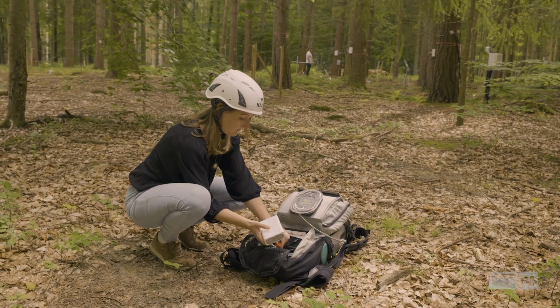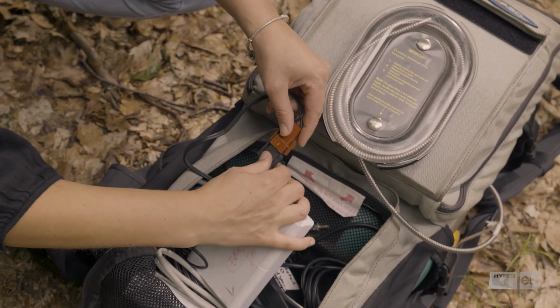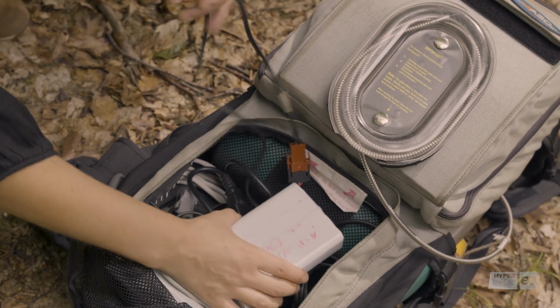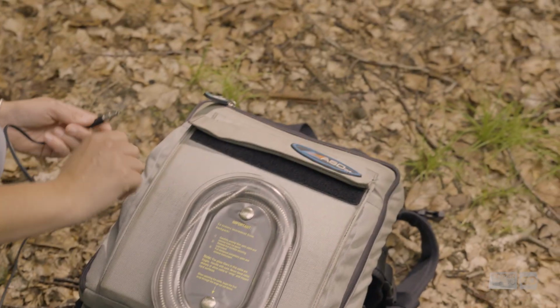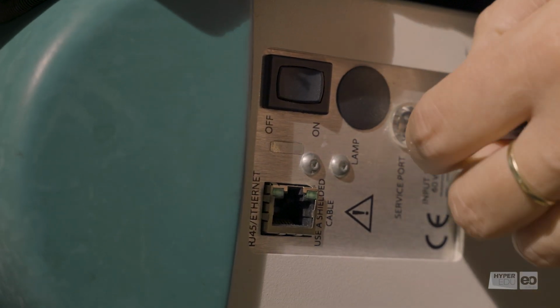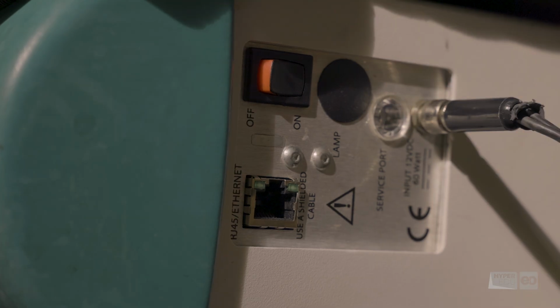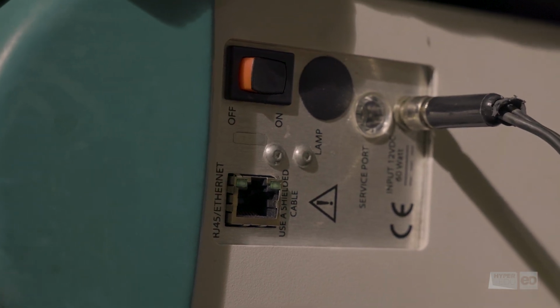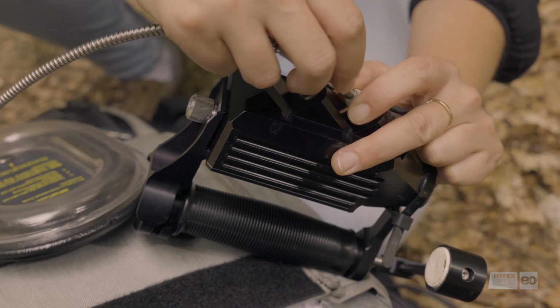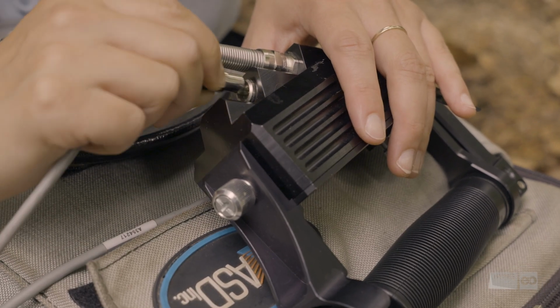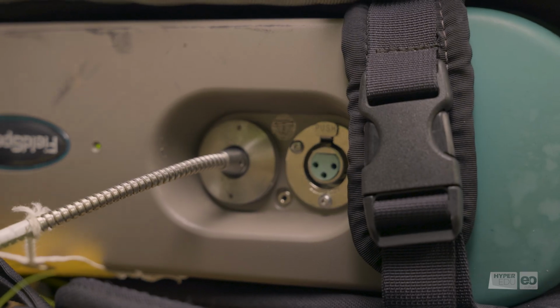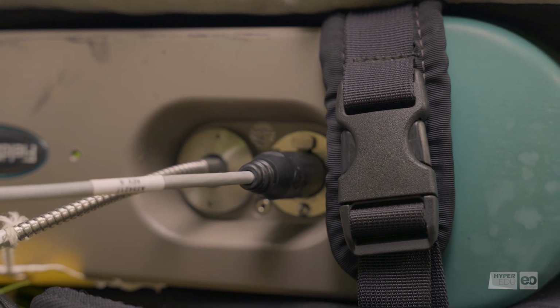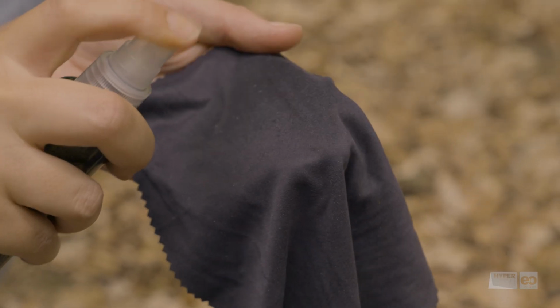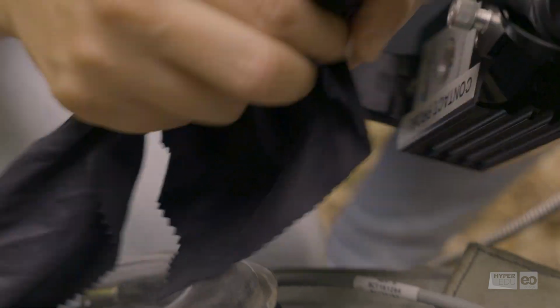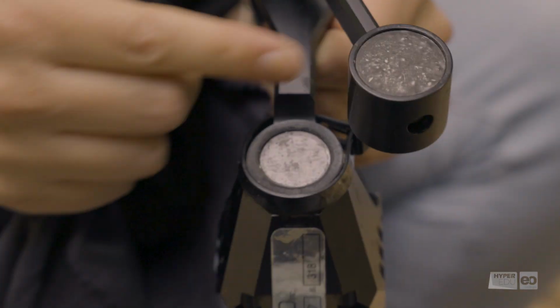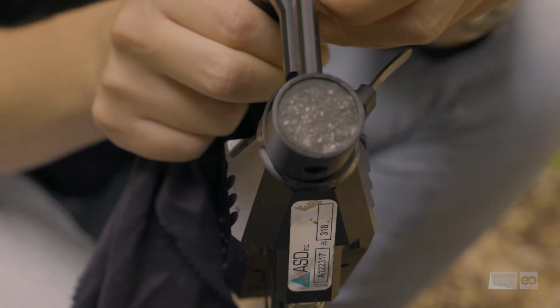Oh, and Pia already unpacked our spectrometer. Once again, it's an ASD FieldSpec 3. Before anything else, she attaches the batteries and switches on the instrument, as it needs some time to warm up. The field spectrometer is quite a versatile instrument that we use in many different setups. Today, we'll use it with a plant probe accessory, including leaf clip. Pia connects the plant probe to the fiber optic cable and to the spectrometer for electricity. This device comes with an internal light source, meaning illumination is always stable and independent of weather conditions. It can even be carried out after sunset.